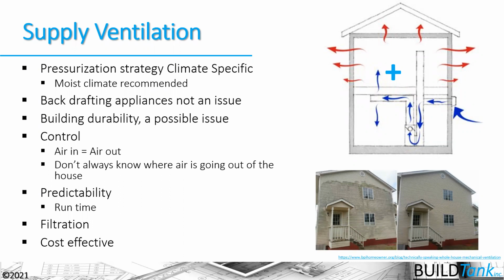So I know the CFM rate, and I'm able to measure that and ensure that I'm getting control of the specific amount of air that's going in and out of the house. I also have predictability because I can set it on a schedule. I can either run it continuously or intermittently, but I know the schedule that I'm putting that air through. I'm also able to filter air that I'm bringing into the house because I'm bringing it in from a known location. I just don't know exactly where it's exiting the house, and that's the potential problem here. It's a cost-effective solution, so you'll see a lot of builders gravitate to this in particular climate zones.